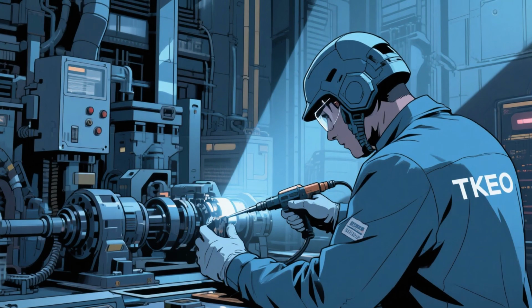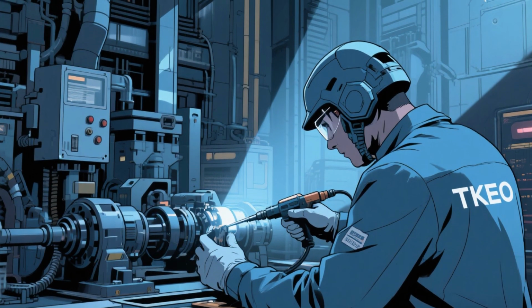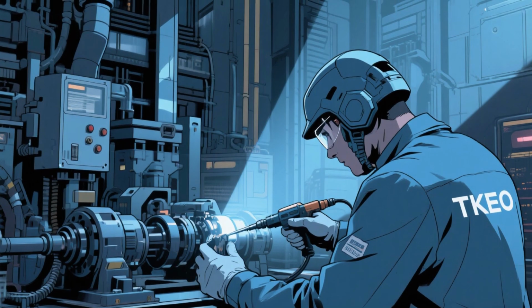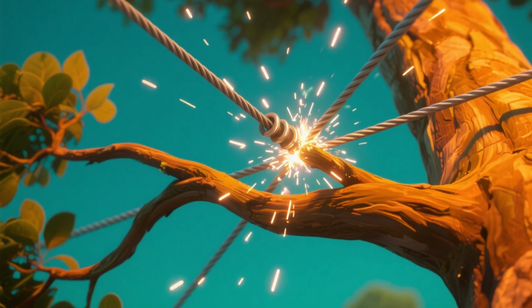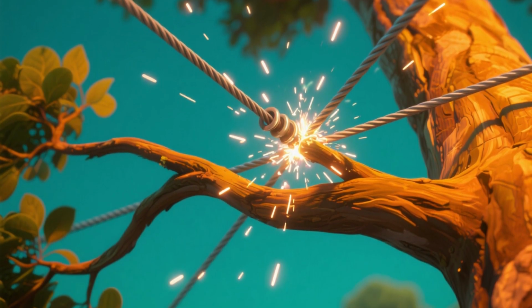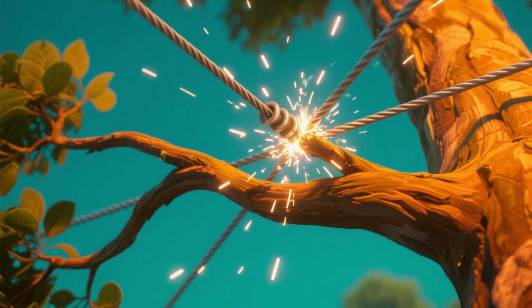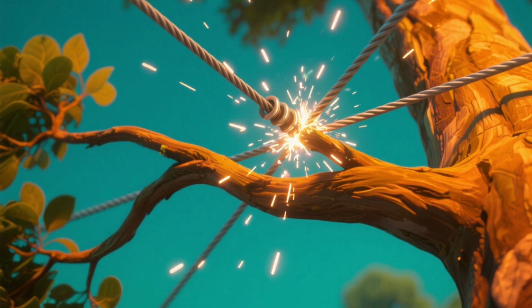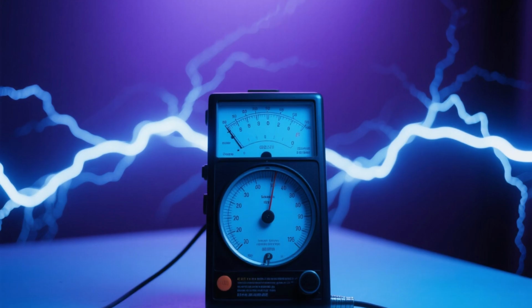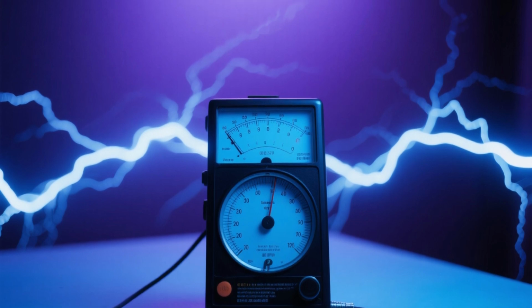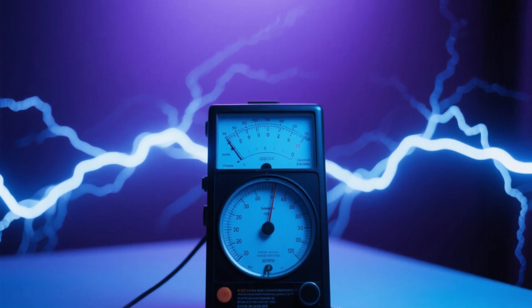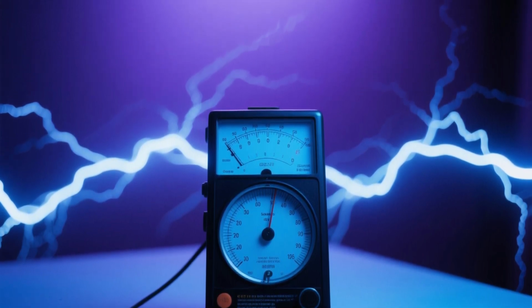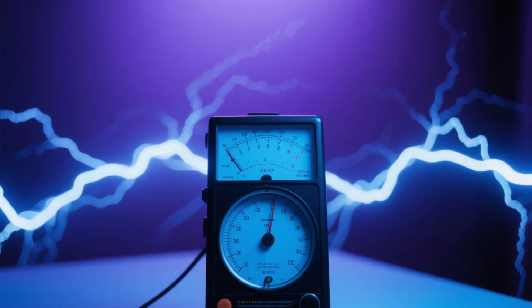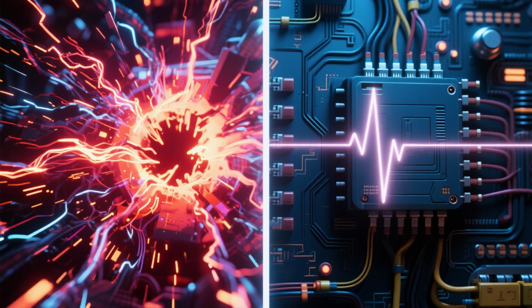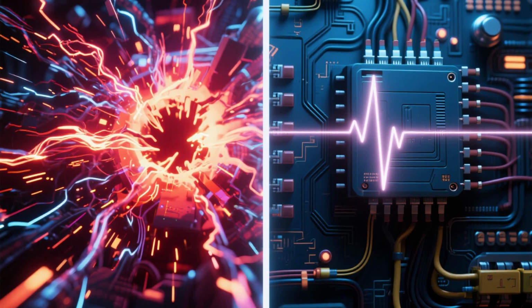One of the key advantages of the TKEO is its robustness, particularly for high-impedance faults. High-impedance faults, also known as high-resistance faults, occur when a live conductor makes a poor connection to ground, for example through a tree branch. These faults produce very small fault currents and can be incredibly difficult for conventional overcurrent or even some transient-based methods to detect. They are like a whisper compared to the shout of a direct short circuit.